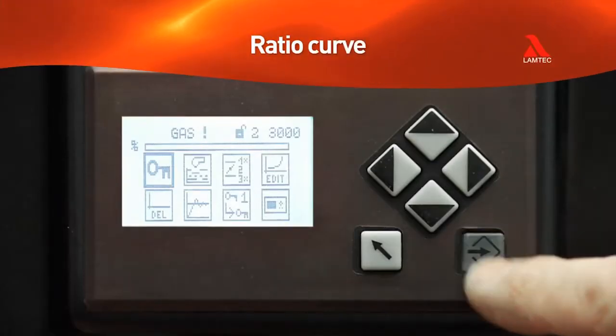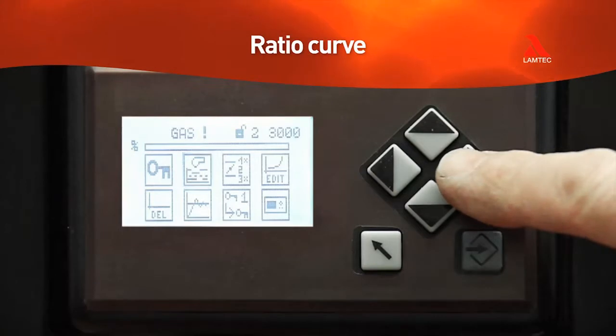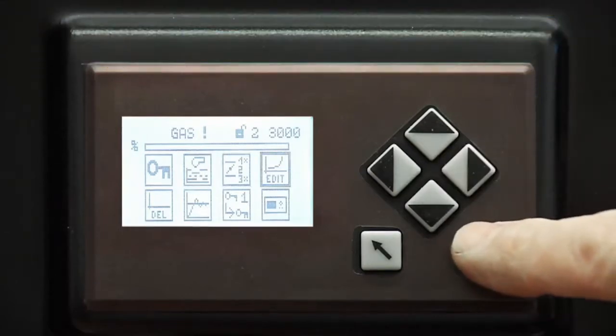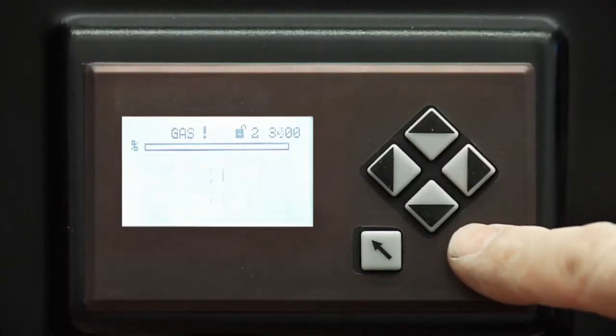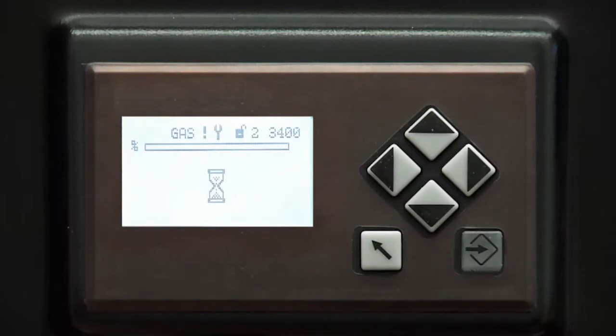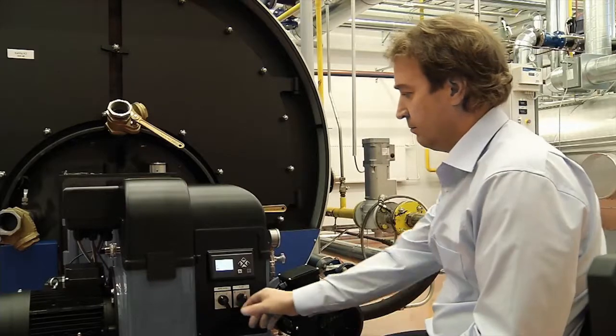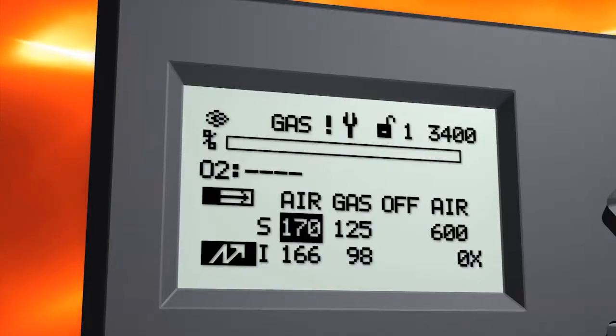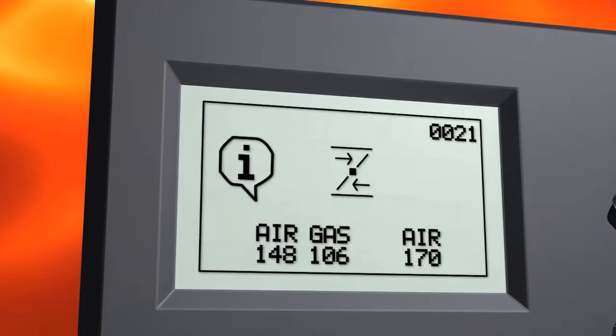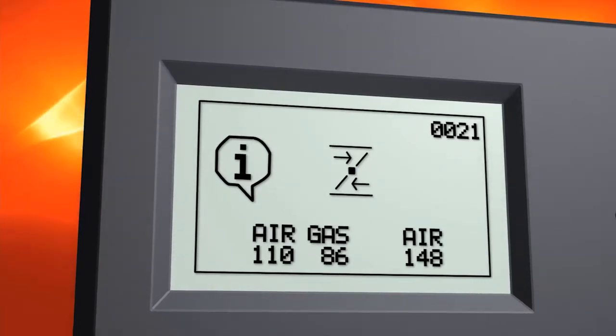Curves are set in the Settings menu. Setting the curve starts with choosing the icon with a curve symbol and the word Edit. Pressing Enter opens the menu and you can set the points. Start the burner. The first point is the ignition point and can be preset.